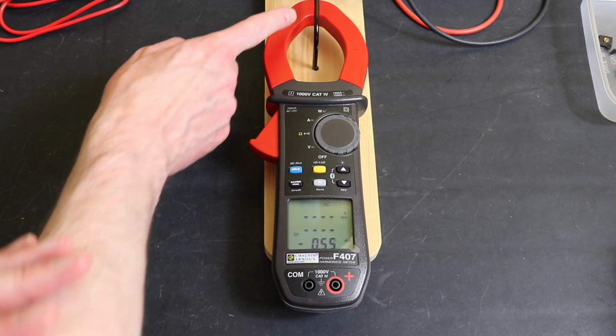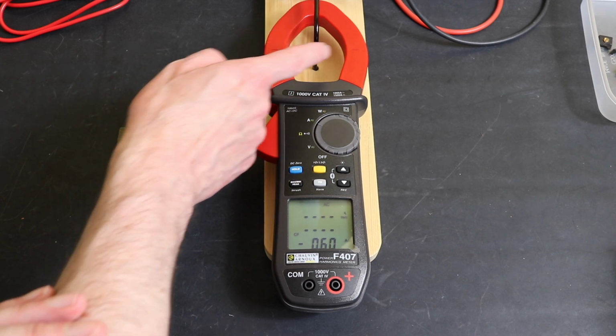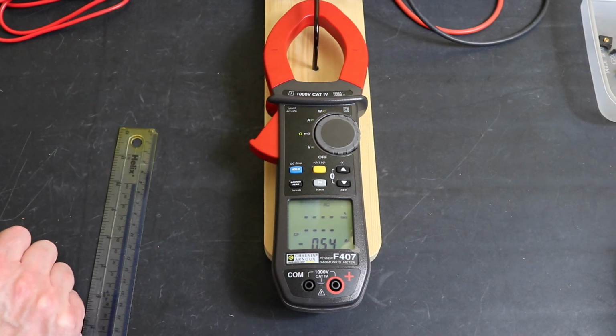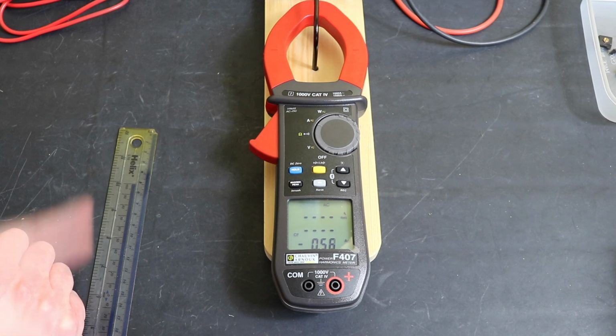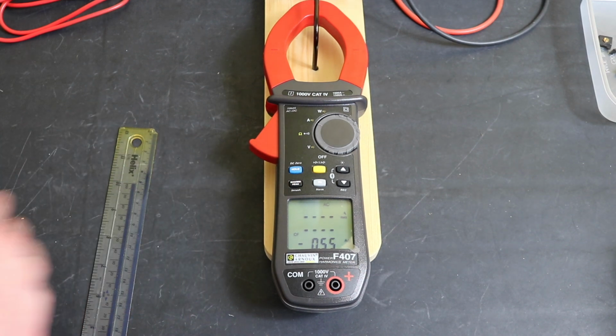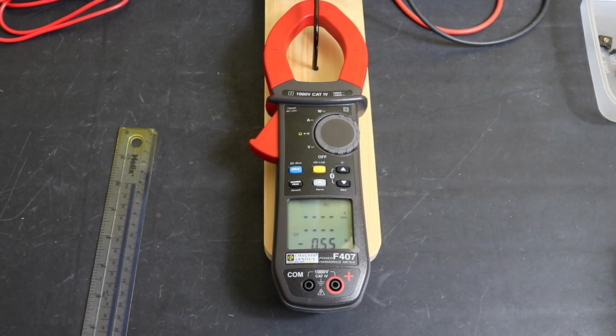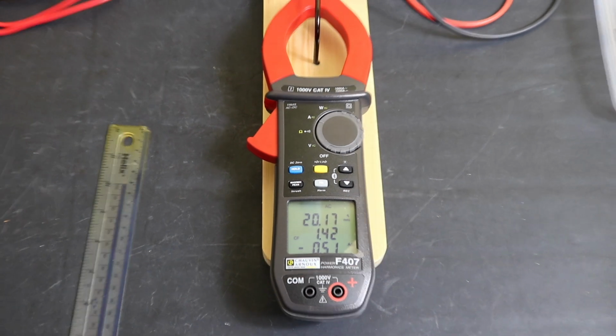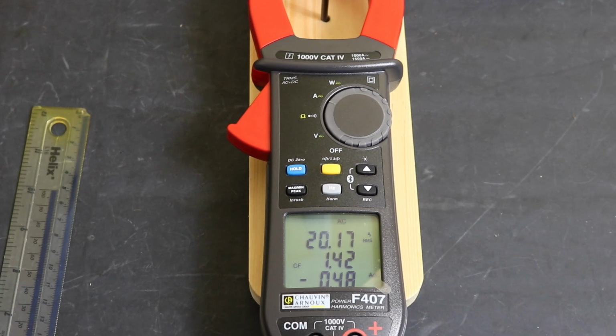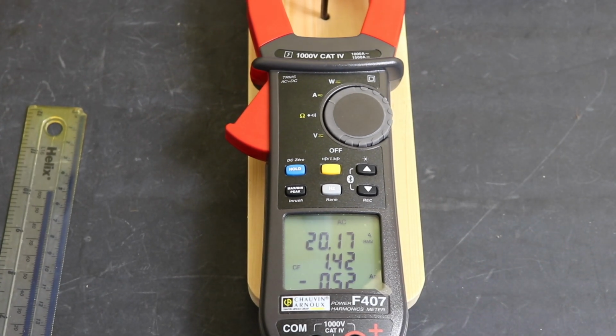This actual clamp size here is quite large. It's 70 mm in height and 50 mm across, the size of conductor that it would take. So we're set to AC. I'm going to inject 20 amps and we'll just move the clamp around and see how much variance we get on the reading. If I can zoom in a little bit, we are reading 20.17 amps at this moment in time.